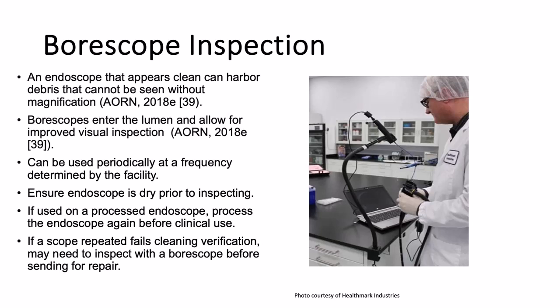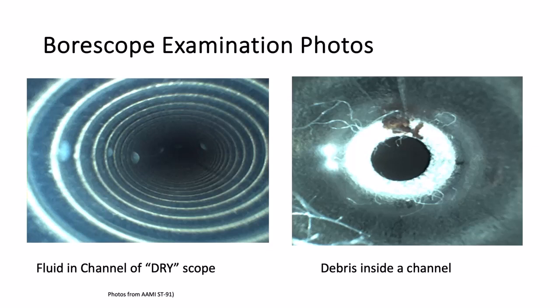Make sure the endoscope is dry prior to inspecting it. And if it's used on a scope that was already processed, you do have to process the scope again, which is why, in my opinion, the borescope should be in the decontam area. And if a scope repeatedly fails the cleaning verification, you may need to inspect it with a borescope before sending it for repair. And here are some examples from AAMI ST91. This is some fluid that was found in a quote-unquote dry endoscope. And of course, fluid is very, very dangerous because of the ability for Pseudomonas and other microorganisms to grow. And this was debris. I mean, just look at all of this inside of a channel of a scope. Pretty nasty. Cleaning verification testing.